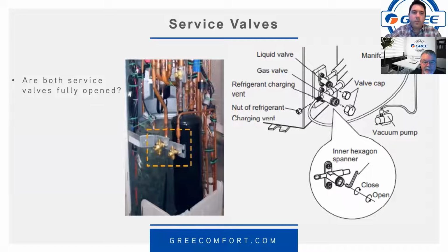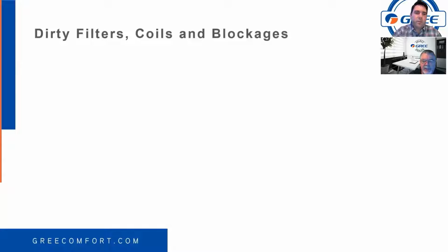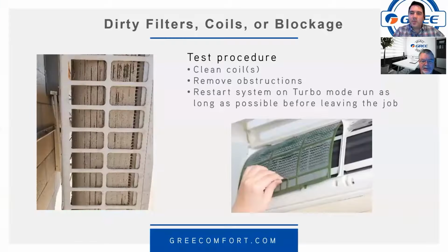Right, right. So the other common thing, this is probably the most common thing, would you say, Daniel? Dirty filters, most certainly. Coils, and some kind of a blockage around the outdoor unit. Sometimes people don't like the way they look, and they'll plant a hedge back there or something, and that's not a good mix. So you know, test procedure for this, visual, obviously.